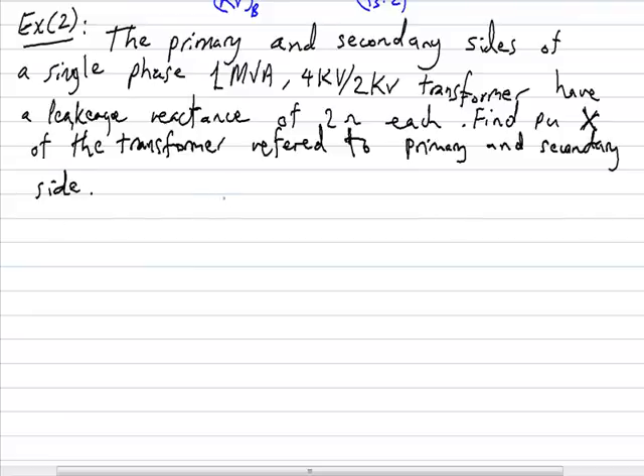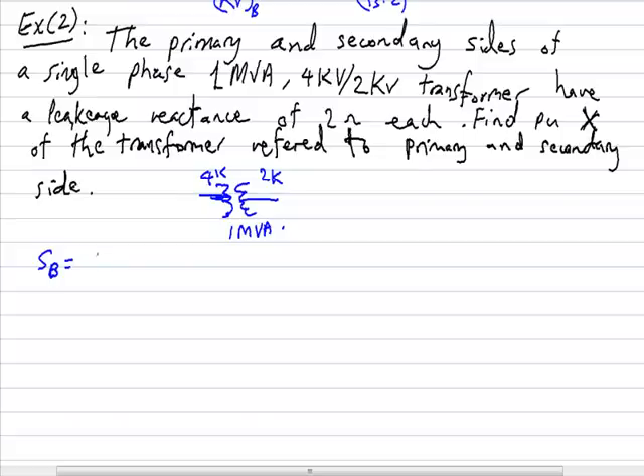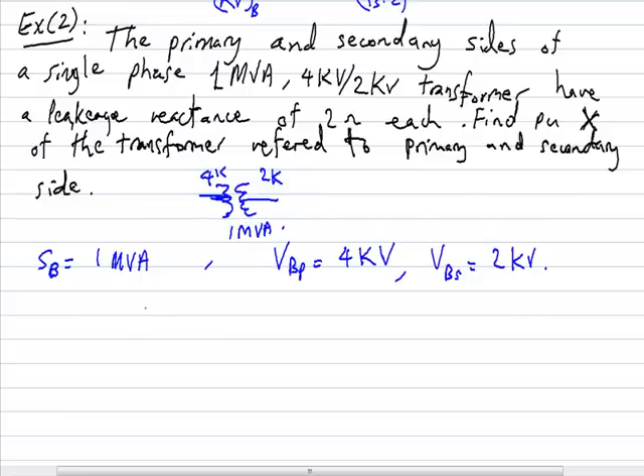As in the first example, we take the rated values of this transformer as the base values. The transformer steps down from 4 kV (primary) to 2 kV (secondary), and it is rated at 1 MVA. Therefore: the apparent power base is 1 MVA, the primary base voltage V_base_primary is 4 kV, the secondary base voltage V_base_secondary is 2 kV. The primary leakage reactance is 2 ohm and the secondary leakage reactance is also 2 ohm.